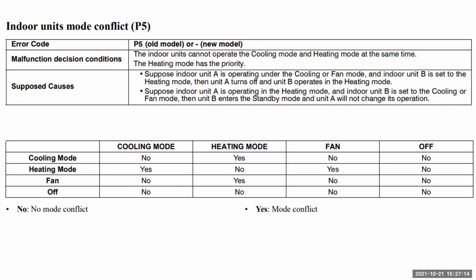P5, old models, mode conflict. Sometimes we also get the double dashes when it comes to this. Like all heat pumps, you can't run it in heat and cool at the same time. So in this case, if we have multiple indoor units, and you're running one in heat and one in cool, you will get this. Sometimes you have to cycle the power in order to get it to reset.